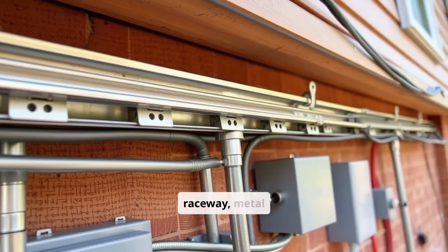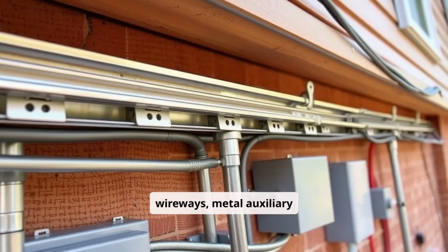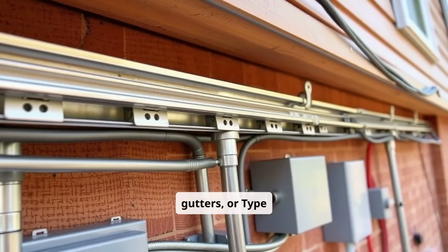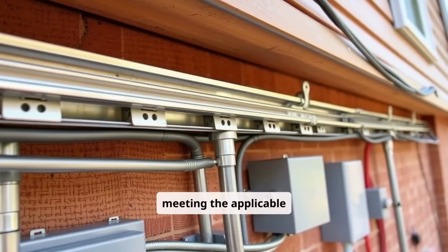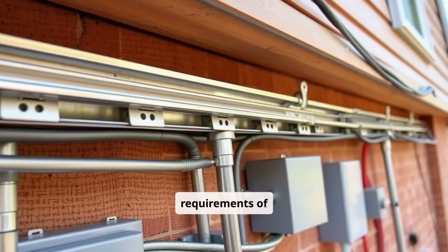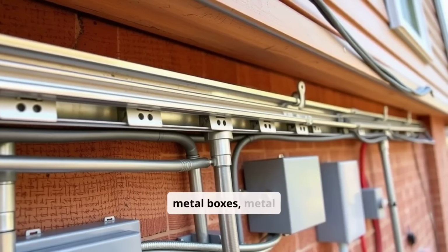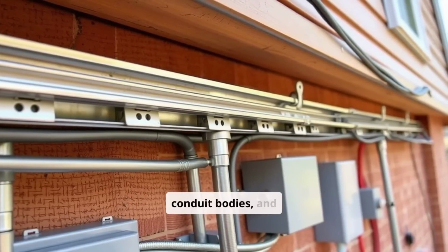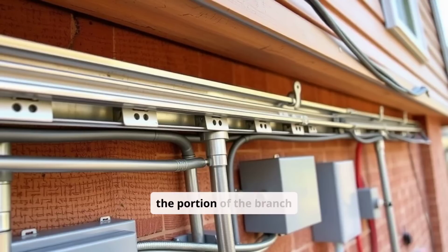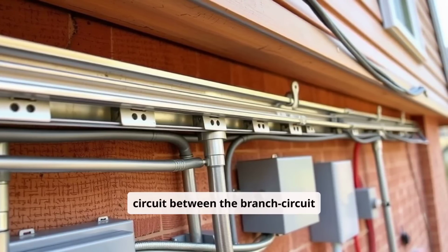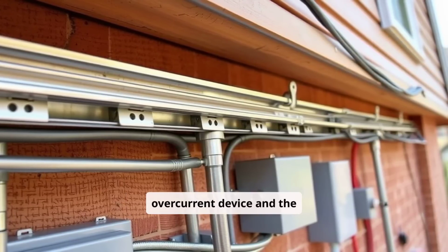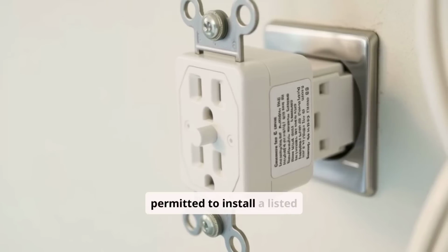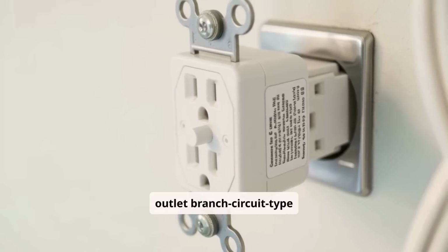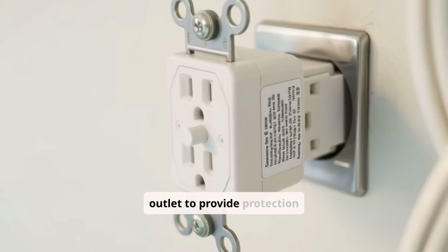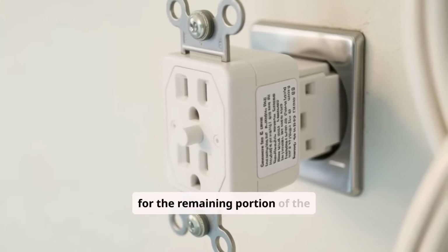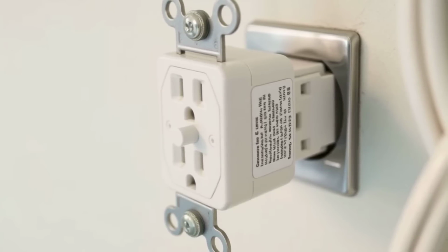5. If metal raceway, metal wireways, metal auxiliary gutters, or type MC or type AC cable meeting the applicable requirements of 250.118, with metal boxes, metal conduit bodies, and metal enclosures are installed for the portion of the branch circuit between the branch circuit overcurrent device and the first outlet, it shall be permitted to install a listed outlet branch circuit type AFCI at the first outlet to provide protection for the remaining portion of the branch circuit.